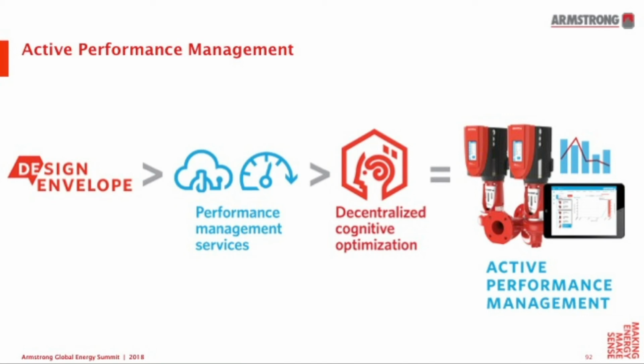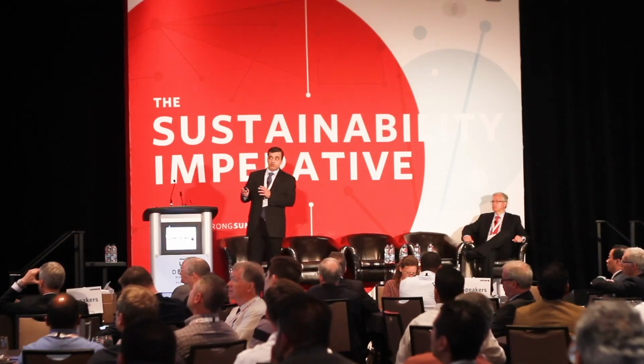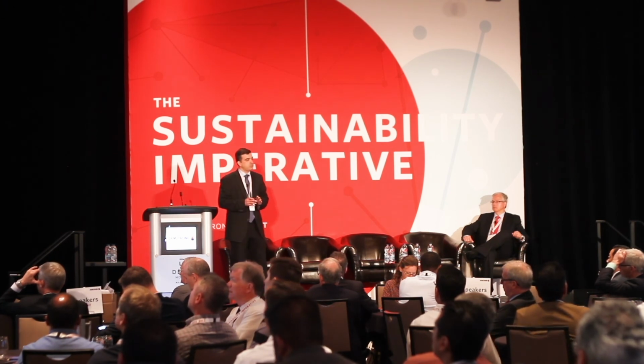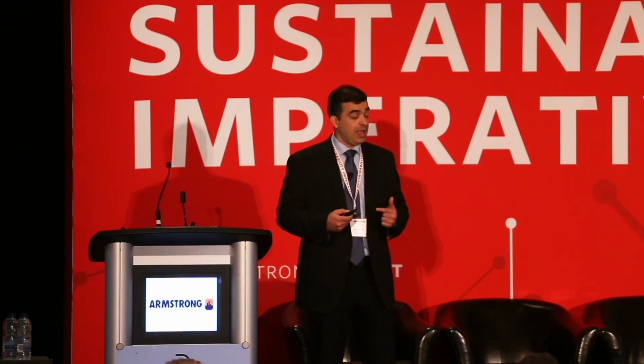That was an important step in decentralizing decision making to support the central control Peter talked about earlier. Combining those three characteristics gives us active performance management, a level above continuous commissioning. Now you're making real-time decisions at a decentralized level, supporting the central control in place. The system never stops learning, it's always analyzing, learning, and predicting, which is extremely important in proactively addressing the energy challenge in the white space.